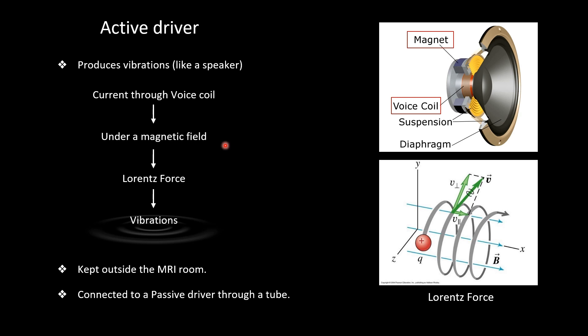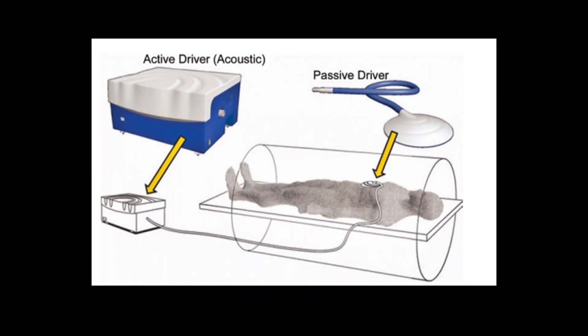Since there is magnetic field production in this setup, the active driver has to be kept outside the MRI room. The active driver which produces the vibrations is kept outside the MRI room. Via a tube, these vibrations are carried to something called a passive driver, which is attached to the body of the patient. The passive driver has no active magnetic field, so it can be kept in the MRI room.